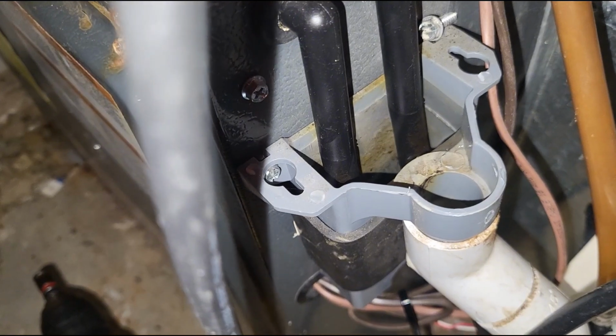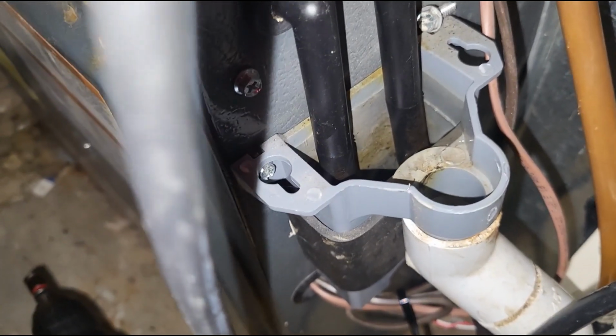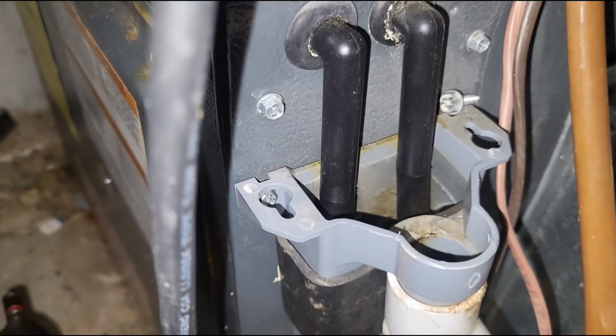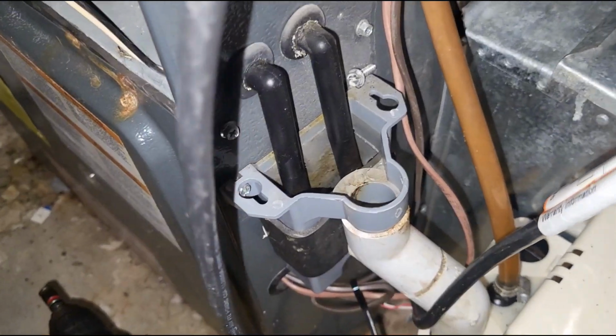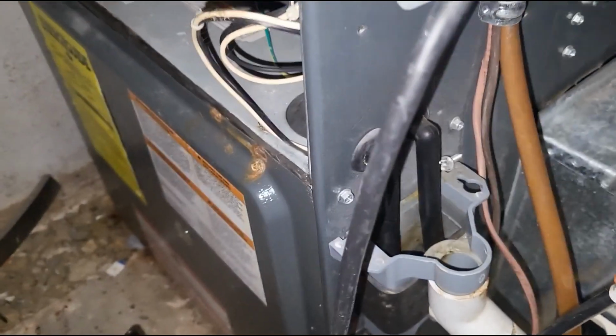is not a dirty filter. It's not one of your components failing. It's the furnace not draining properly. Either the condensate trap can be blocked up, or maybe the condensate drain from your furnace could be pitched incorrectly or clogged up as well. So you want to make sure that this is actually draining properly. That's what I'll do now.